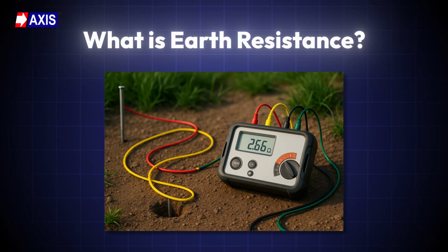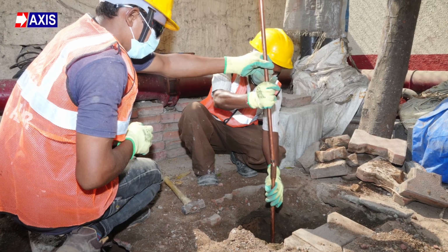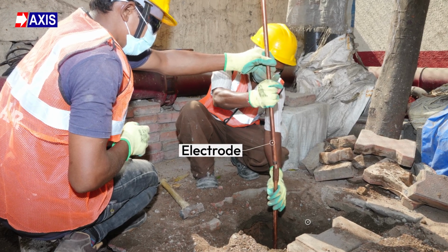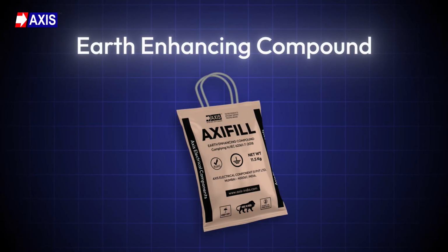Earth resistance. Earth resistance is the measure of how easily electrical current can flow from an electrode into the ground. Lower resistance ensures faster and safer dissipation of faulty current. This resistance depends mostly on soil resistivity. To keep the value within safe limits, the soil around the electrode must be stable and conductive enough to allow proper current flow. That's where earth enhancing compounds help.